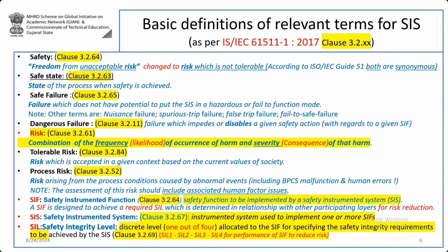But you do not know. And if it fails dangerously, that means that level transmitter was supposed to give you an alarm for the high level in the reactor, and the transmitter has failed and doesn't give you an alarm for the high level. It's a dangerous failure, the dangerous undetected failure. You also do not know whether the transmitter has failed or not. So for a dangerous undetected failure, if it is a single transmitter and it fails in a dangerous mode, you will lose the safety with respect to the safety instrumented function or safety instrumented system, whatever you call it.